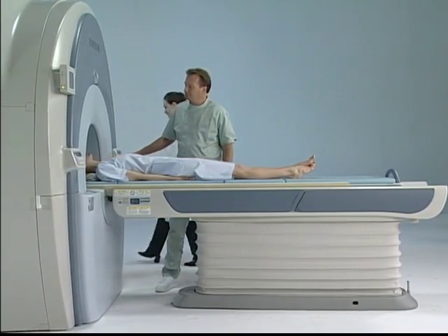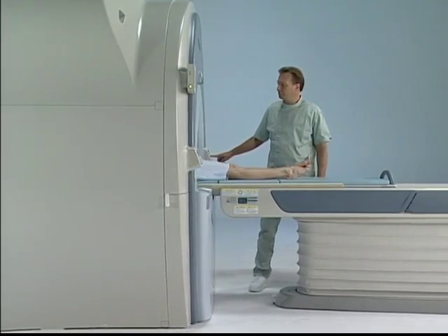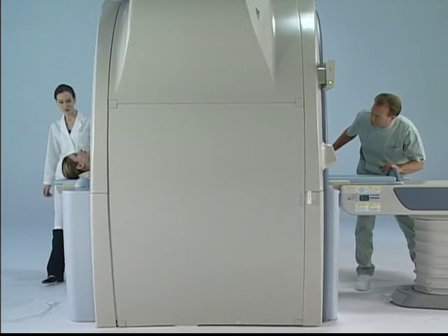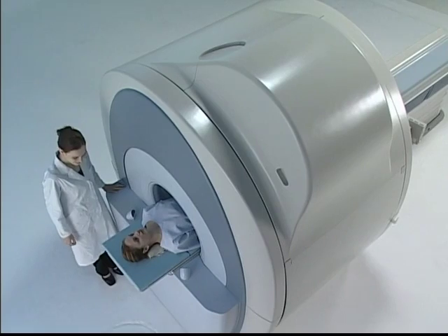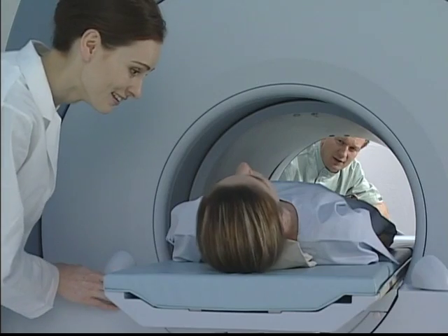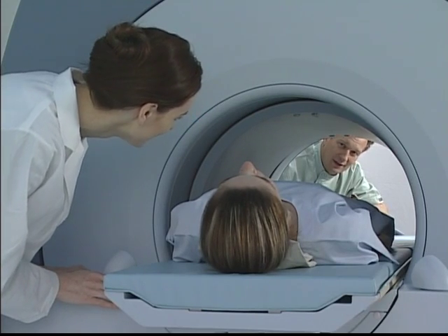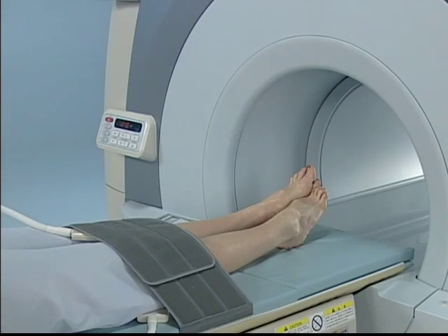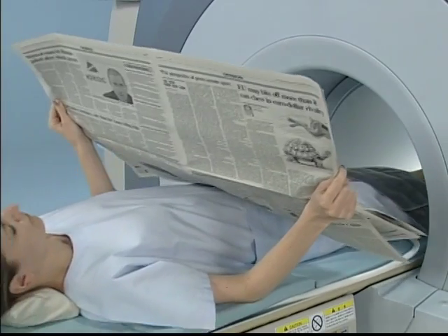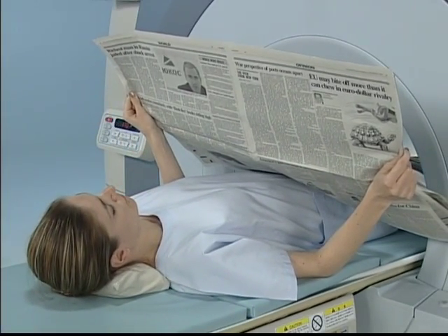Excelart Vantage is a maximum 50 centimeters shorter than other MRI systems of the same class. No more must patients endure the long, dark tunnel for an abdominal or pelvic exam. A wide opening adds even more to the patient's feeling of openness and comfort. To achieve a gantry of such open design, Toshiba had to reinvent MRI technology and overcome technical challenges of great difficulty.